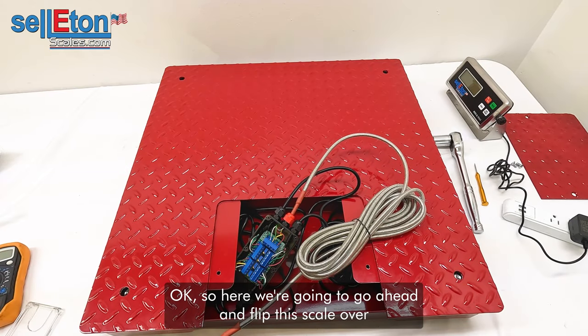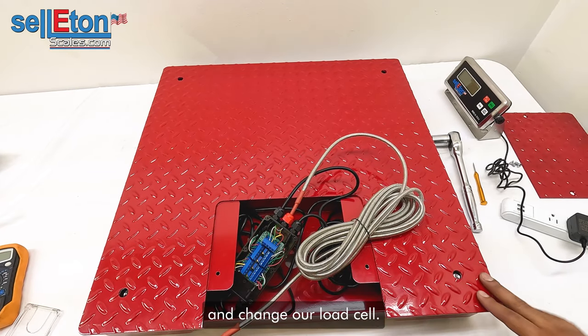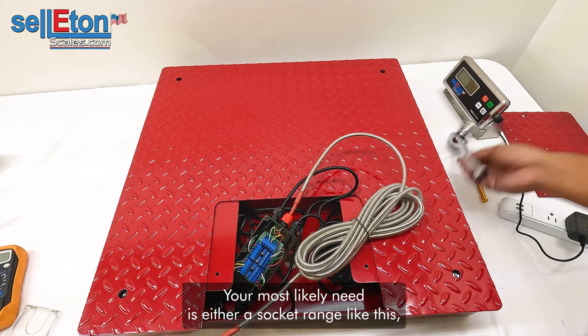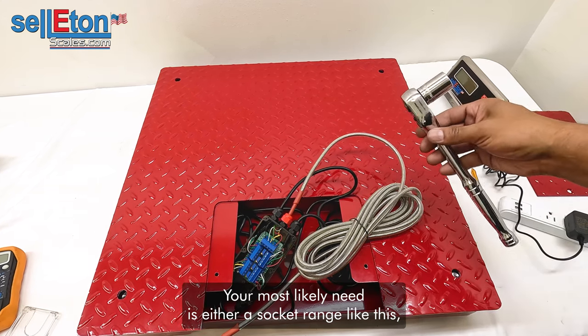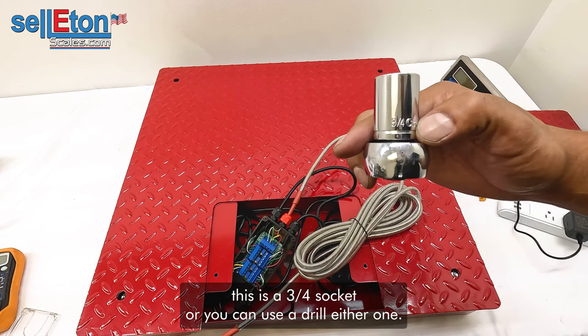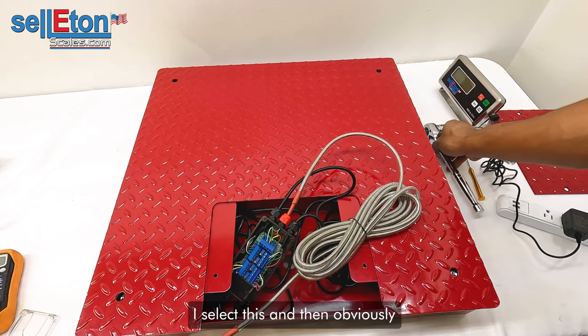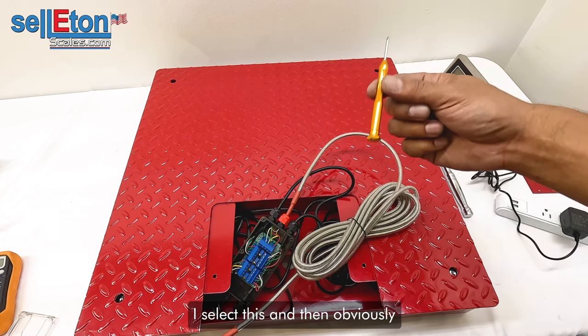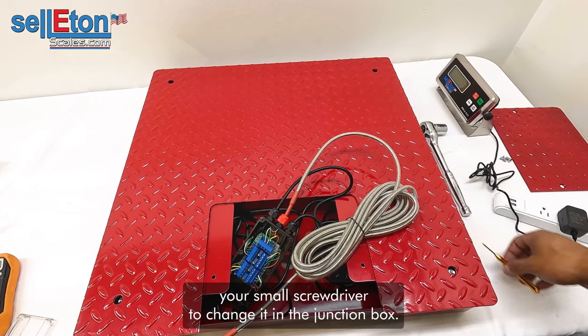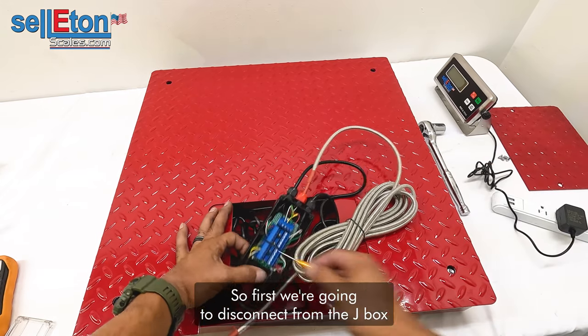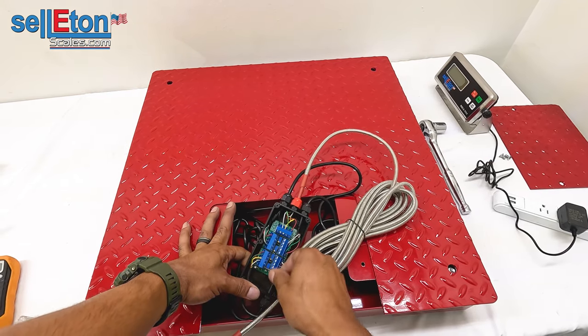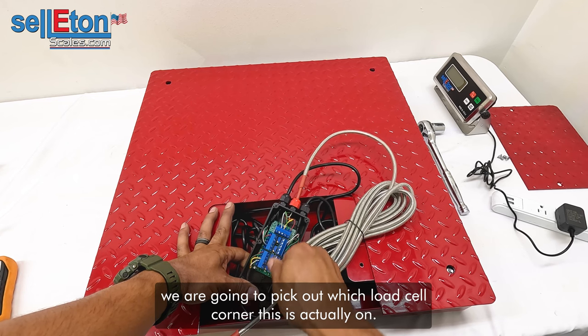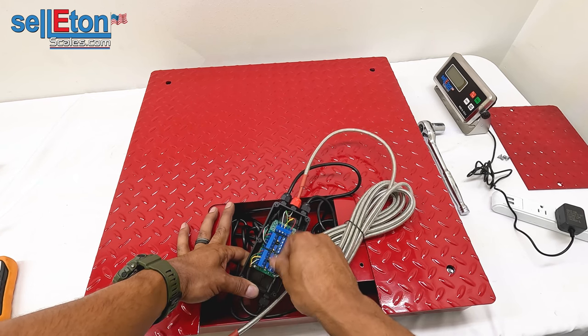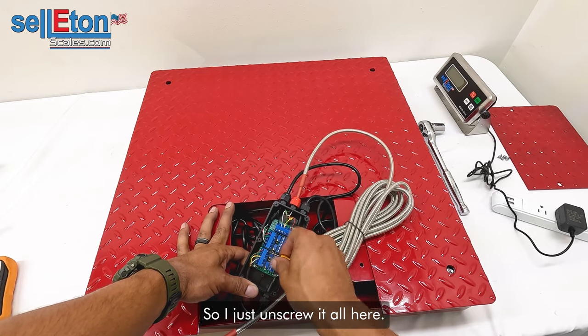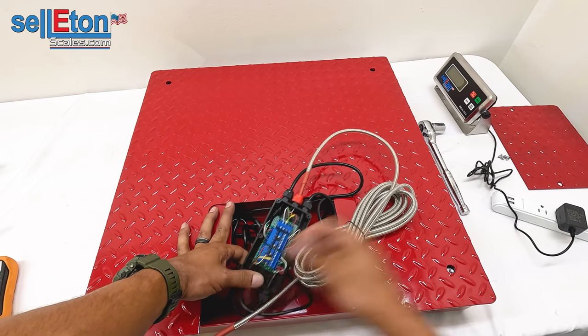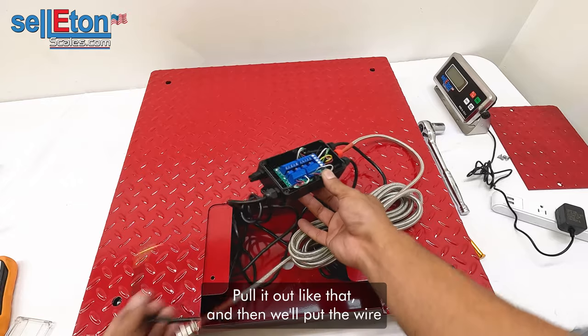So we're gonna change this load cell. Here we're gonna go ahead and flip the scale over and change our load cell. The item you'll most likely need is either a socket wrench like this. This is a 3/4 socket, or you can use a drill, either one. I just have this. And then obviously your small screwdriver to change it in the junction box. So first we're gonna disconnect from the J box and we're gonna figure out which load cell corner this is actually on. So we'll just unscrew it all here. We'll pull it out like that and then we'll pull out the wire.